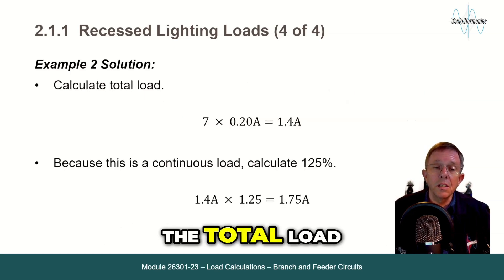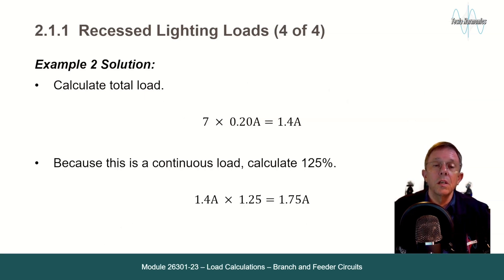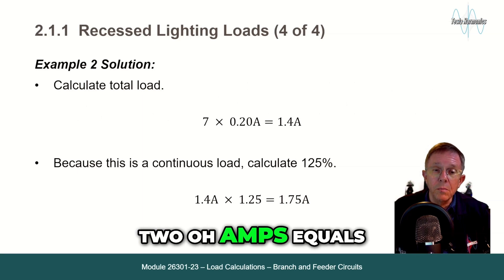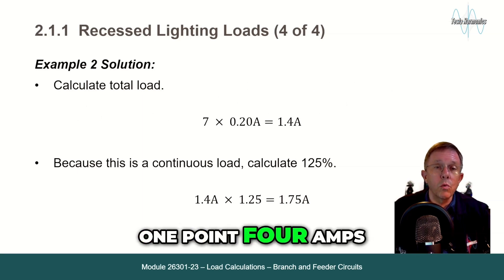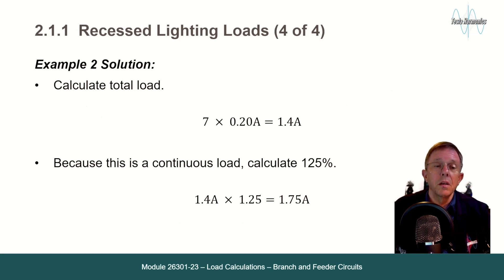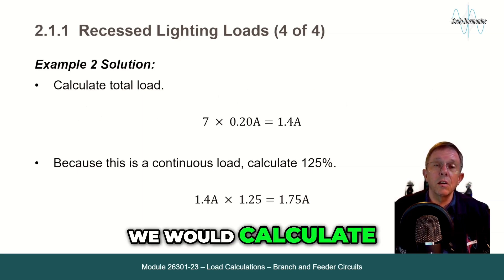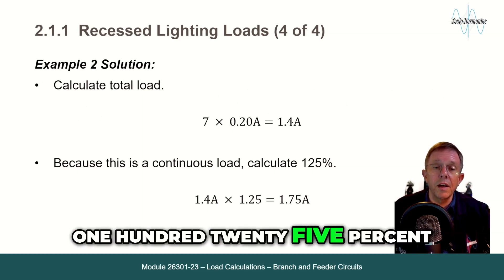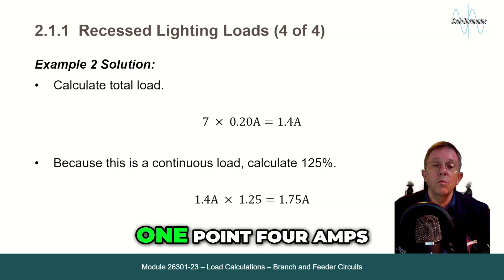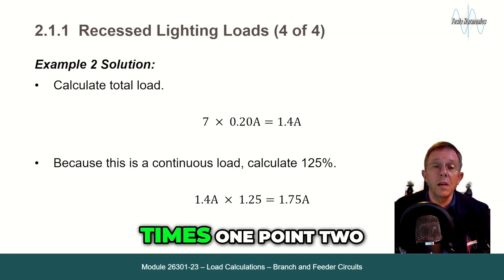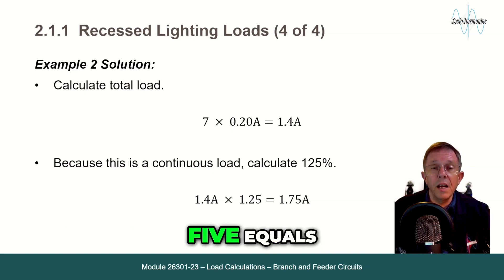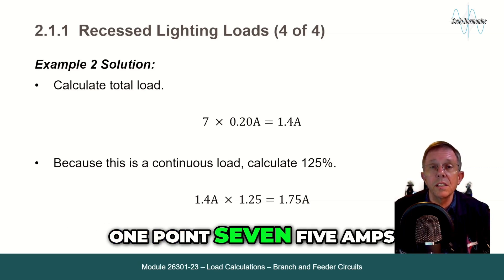We would calculate the total load: 7 times 0.20 amps equals 1.4 amps. Because this is a continuous load, we would calculate 125%. 1.4 amps times 1.25 equals 1.75 amps.